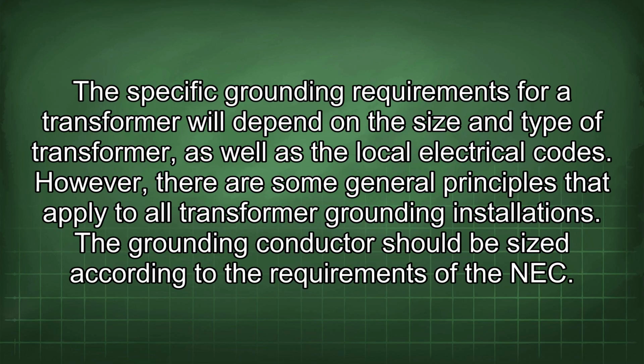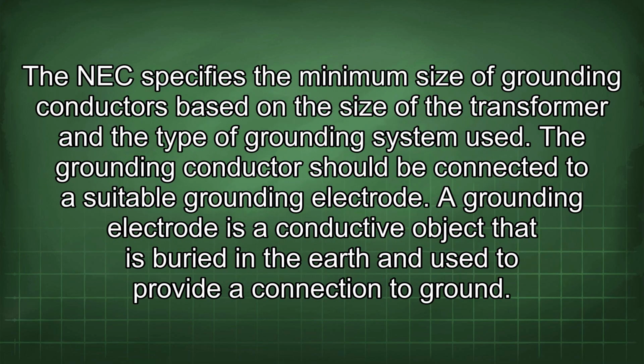The specific grounding requirements for a transformer will depend on the size and type of transformer, as well as the local electrical codes. However, there are some general principles that apply to all transformer grounding installations. The grounding conductor should be sized according to the requirements of the NEC. The NEC specifies the minimum size of grounding conductors based on the size of the transformer and the type of grounding system used. The grounding conductor should be connected to a suitable grounding electrode.